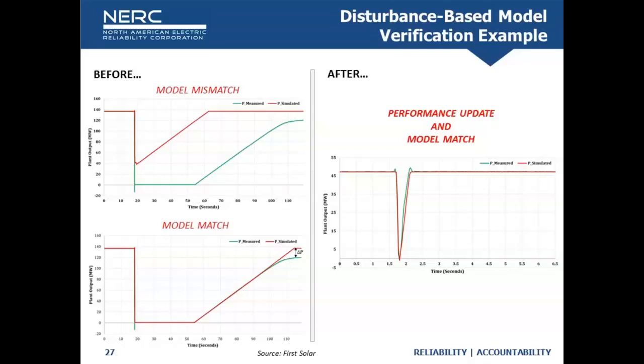The main issue was that the model didn't match reality. Their first task was to get that model to match so they could provide it to their planner and make them aware. In the bottom left, you can see they modified some settings in the generic model and got a nearly perfect match. There's a little mismatch at the end due to partial tripping of individual inverters within the plant, which isn't accounted for in the positive sequence simulation generic models—so that's expected and explainable. Overall, that match is pretty great.